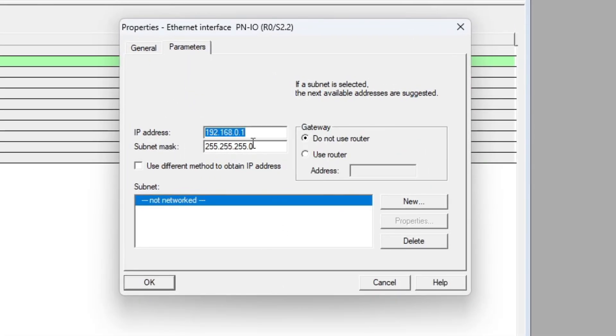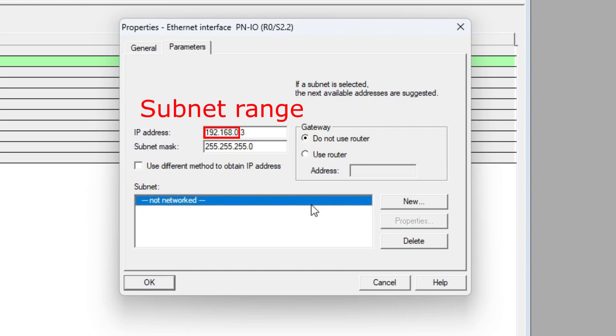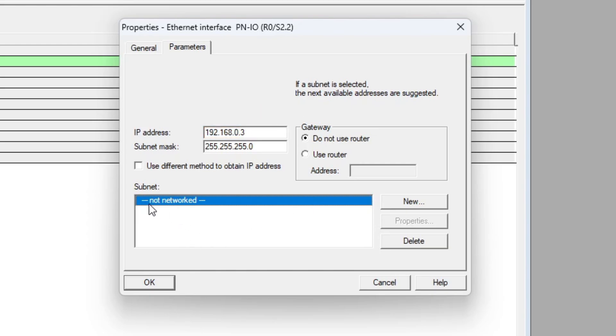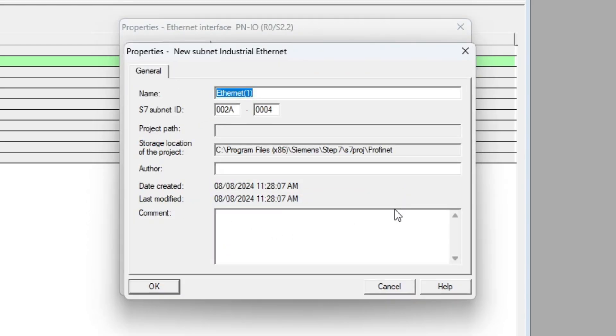When we add the PLC we get to choose an IP address. Note that the first three parameters of the PLC have to be in the same subnet range as the other stations in the Profinet connection. Then we want to click on New to add a new Profinet subnet. We can give the network a name if we want to.